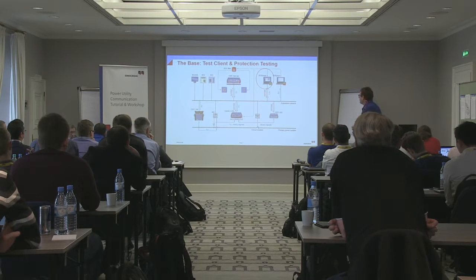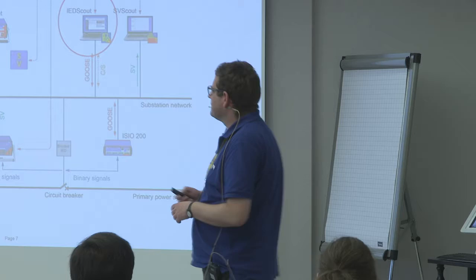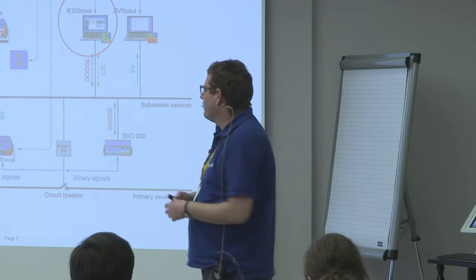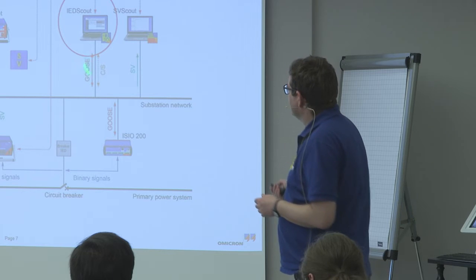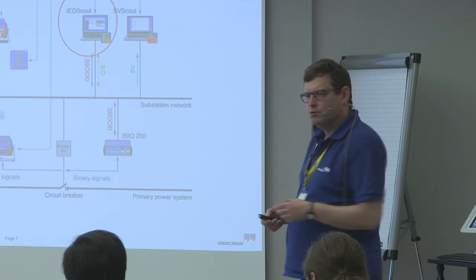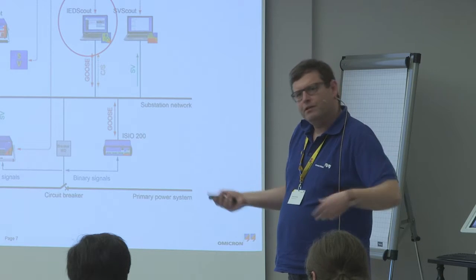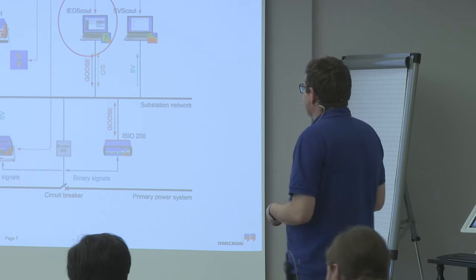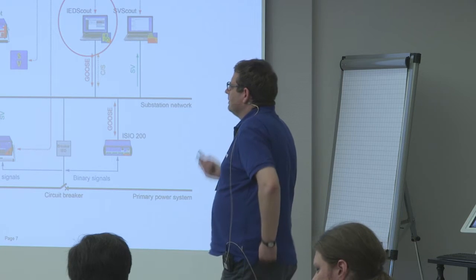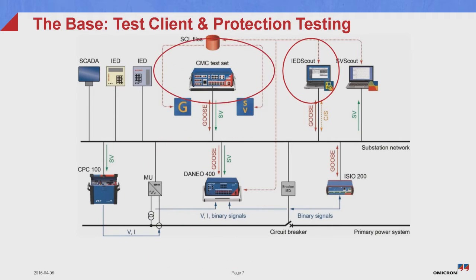We have had this product here, you see the IEDScout, for a long time, and it is performing exactly those tasks. This software is also capable of handling GOOSE, so you can visualize the GOOSE because you receive it anyway; you connect your computer, and you can work with that. But the next task is then to talk about protection testing. What do you do if you want to connect the test set?